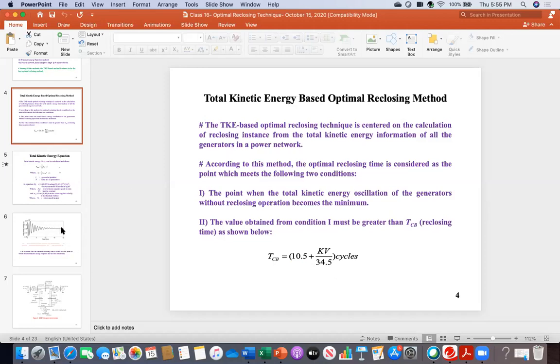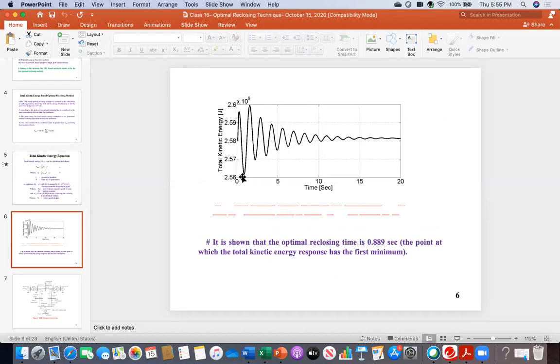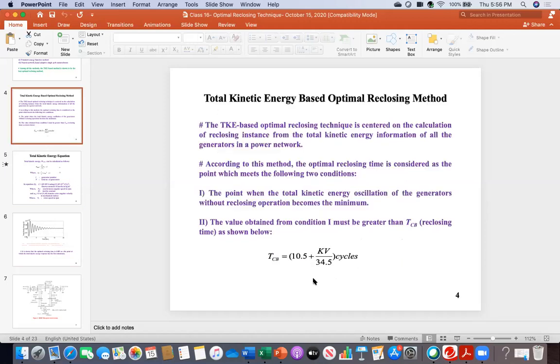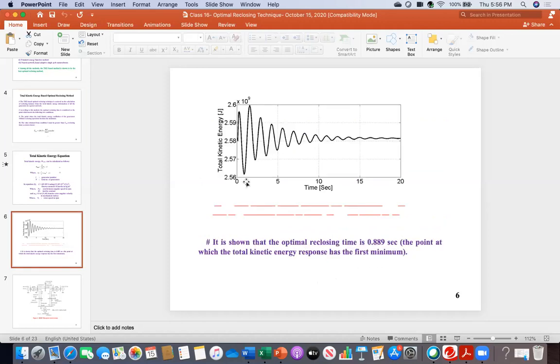Now the condition is met properly. As I said, the first minimum point is 0.889 seconds. This time is bigger than what we are getting here, 0.221 seconds. So now you can reclose the breaker at this point.